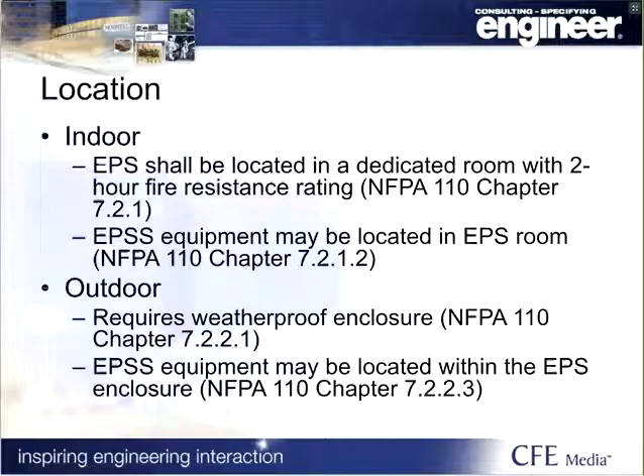NFPA 110 7.2.1 requires the space to be dedicated to the EPS and have a 2-hour fire resistance rating. Other EPSS equipment, such as the generator distribution and transfer switches, may also be located in the dedicated EPS room. If the EPS is located outdoors, NFPA 110 requires an enclosure that provides protection from the elements. The standard allows other EPSS equipment to be located in the enclosure, but this is typically limited to a couple of 1 or 2 circuit breakers, and all the other equipment is located indoors due to space constraints.